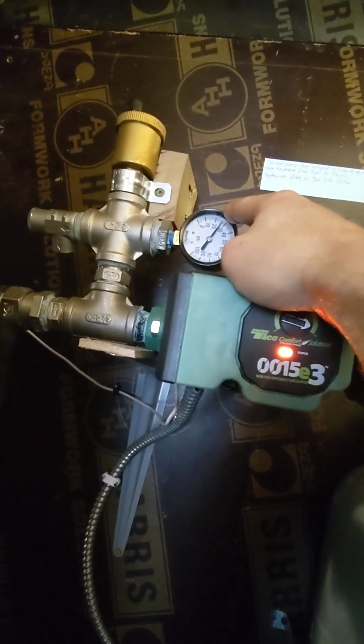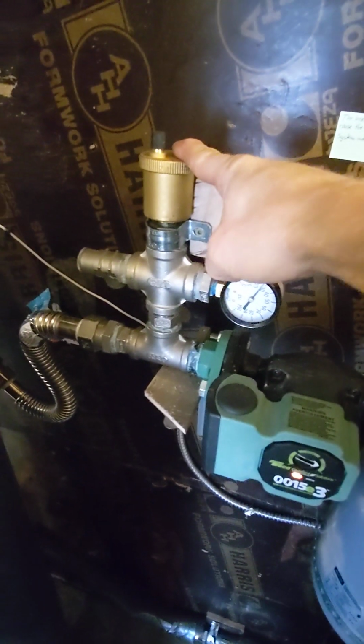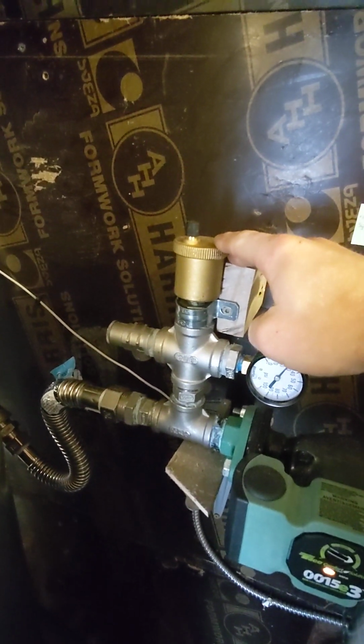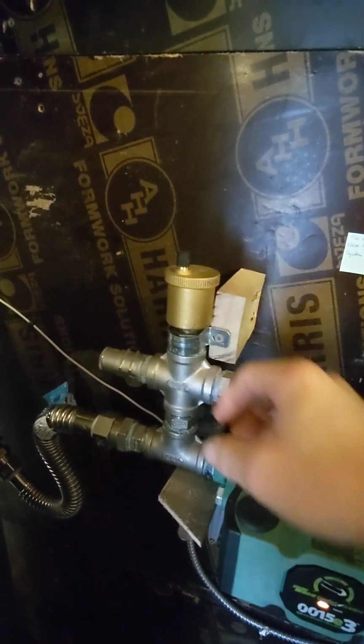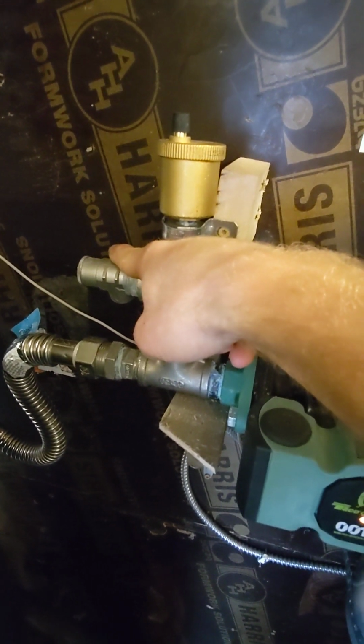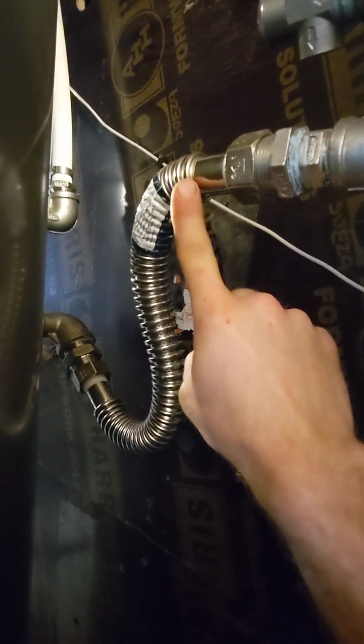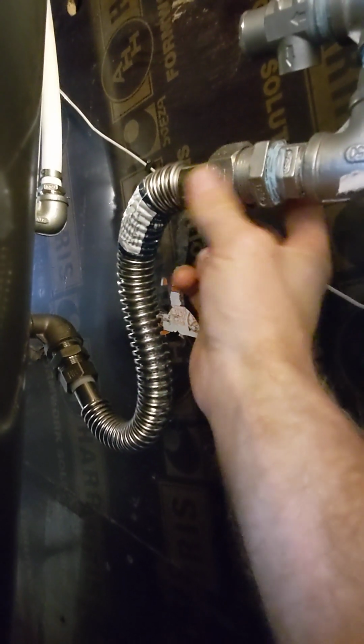Then we have a pressure gauge to keep the system pressure monitored, and another air separator valve because it's the highest point in my entire system, so air pockets don't collect in any high spots. Then here a pressure relief valve, and then the water heater connectors, stainless steel, that just screw onto these fittings here and here.